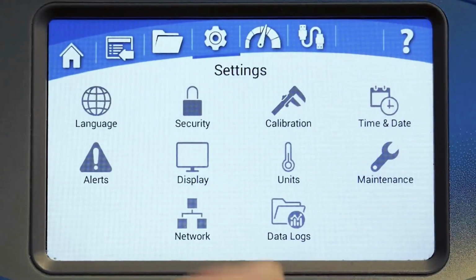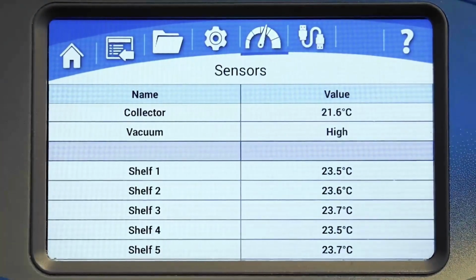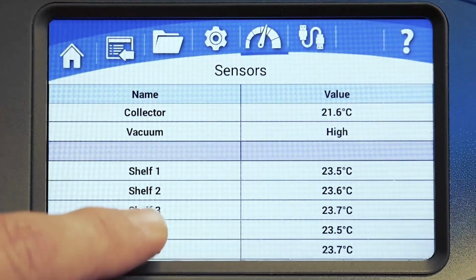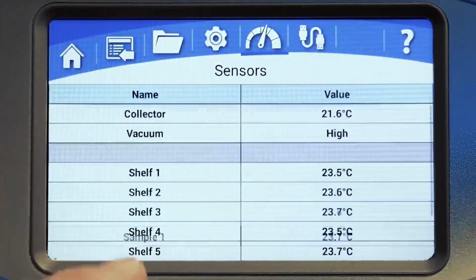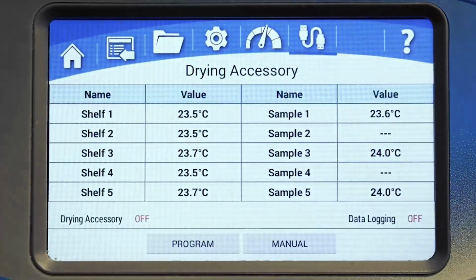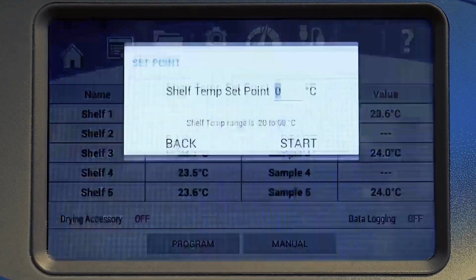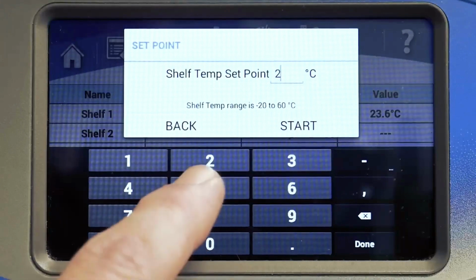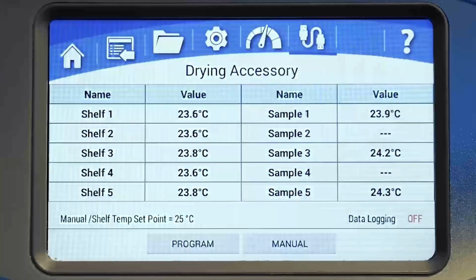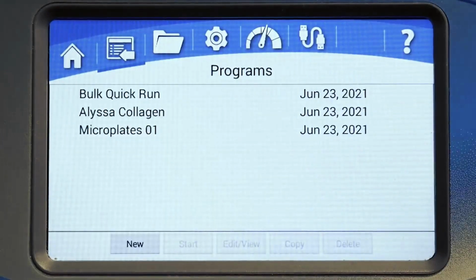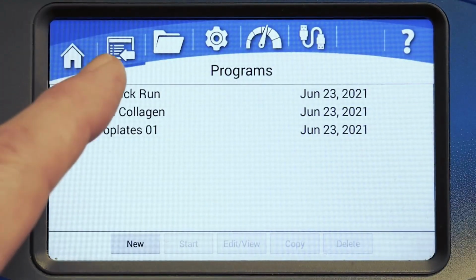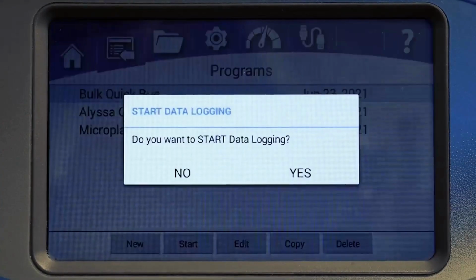The Sensors screen displays a list of current readings for all sensors and accessories installed on your FreeZone. The Drying Accessories icon will appear only when a plug-and-play accessory is connected to your freeze dryer. Here, you can view the sensor's readings for drying accessories such as heated shelves and tray dryers. Use the Manual button to enter a set point temperature or start the accessory in manual mode. The Program button will take you back to the Program screen, where you can create and edit programs that include your accessory's shelf temperature settings.